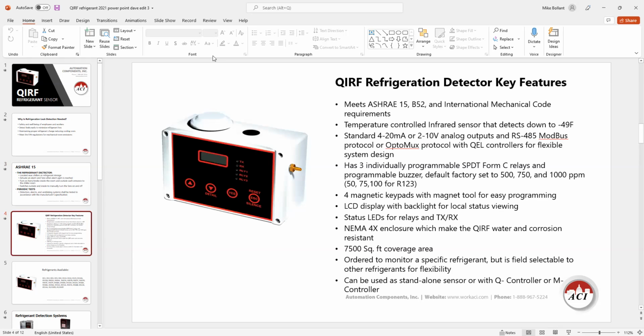QIRF refrigerant detector. It's infrared technology. The sensor has a lifespan of about 13 years. It covers about 7,500 square feet. Comes with 3 relays and an LCD, all preset. And the cool thing about this is, let's say you have a QIRF on your shelf and a customer comes in and says this is set up for R134A and you need R510. Well, you don't have to send that unit back or order a different one. You can just power it up and change the parameter right on the screen to an R510.